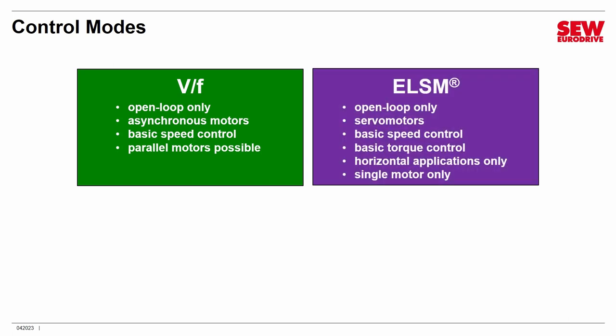The next mode is one that really gets us excited — it's brand new, called ELSM, which stands for Encoderless Synchronous Machine. I like to think of it as Encoderless Servo Motor, which is easier to remember. This is an open loop servo motor control mode, and it's what you use with those encoderless servo motors. It gives you basic speed control and basic torque control with a servo motor that does not have any kind of feedback device, and it does a pretty nice job. So if you need to use a servo and don't want to pay for an encoder, put it in ELSM mode in the VFD and it will handle it.